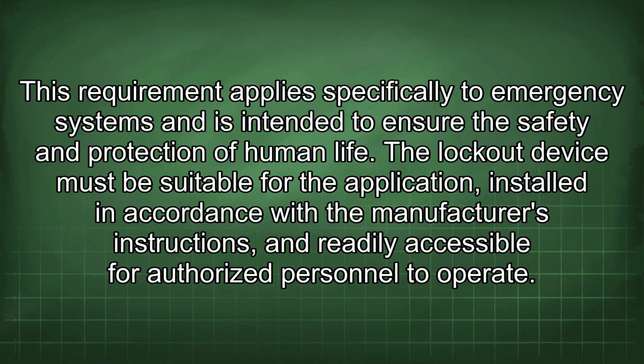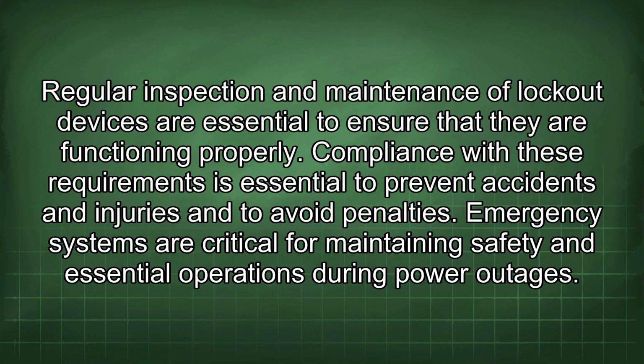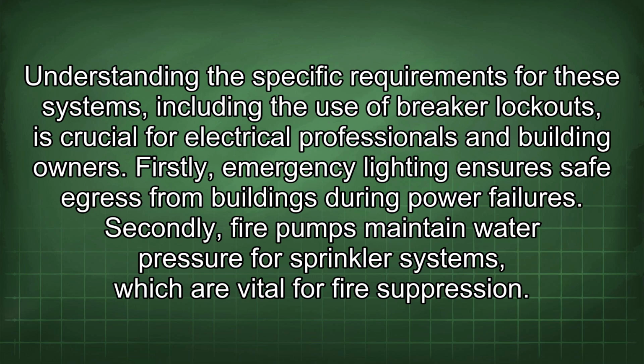The lockout device must be suitable for the application, installed in accordance with the manufacturer's instructions, and readily accessible for authorized personnel to operate. Regular inspection and maintenance of lockout devices are essential to ensure that they are functioning properly. Compliance with these requirements is essential to prevent accidents and injuries and to avoid penalties. Emergency systems are critical for maintaining safety and essential operations during power outages.